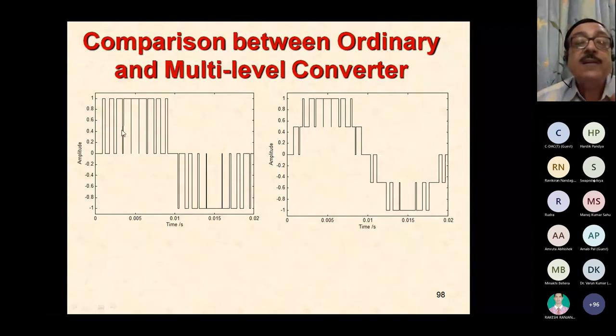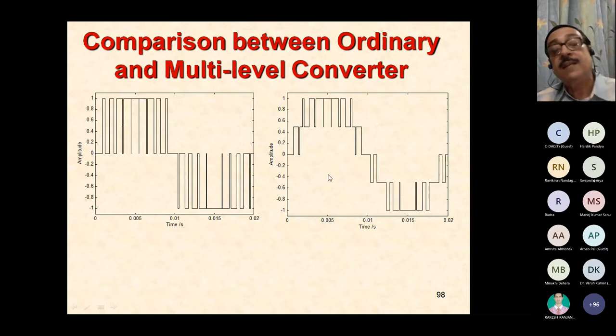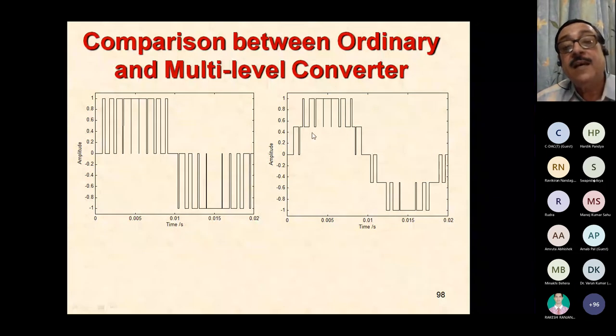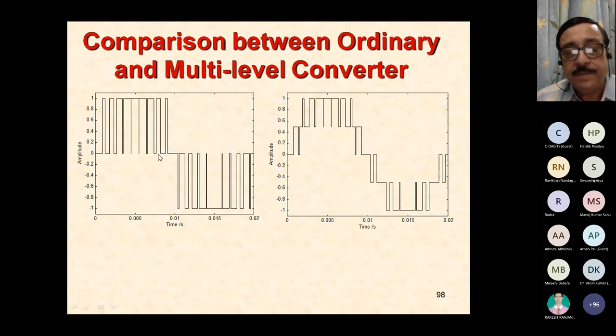When you take a closer look at the system between the ordinary, basically two-level, and the multi-level inverter, there are certain other points that you'll find. Apart from the voltage that you see, you can see this is cutting down to zero during the positive half cycle. Here, you will not see it cutting down to zero. The magnitude is one per unit, but here it is cutting down only 50%. So the dV by dt created by the inverter is only 50% of what was here. Plus you get more fundamental, because this is a rock solid area. Nothing has been cut out from this area. So you get higher fundamental also.